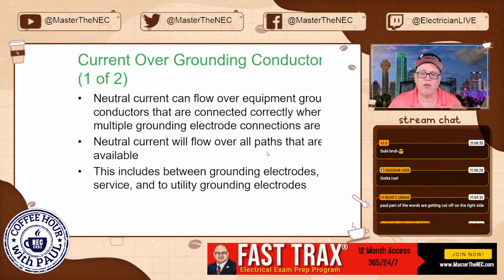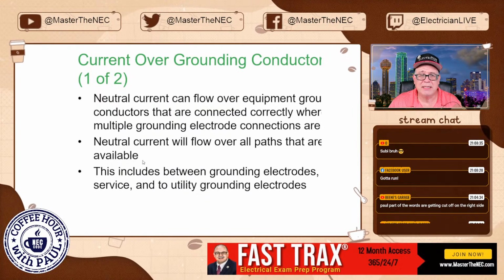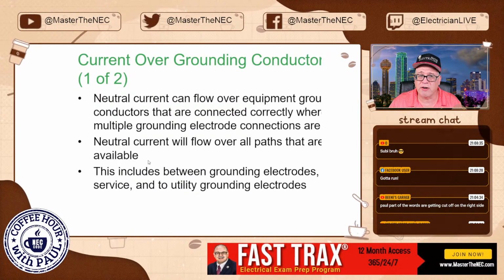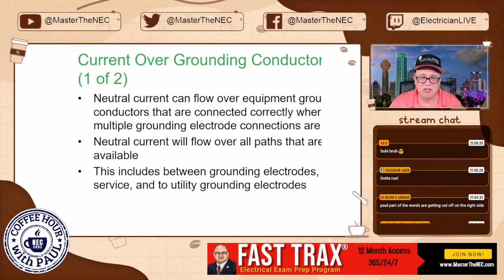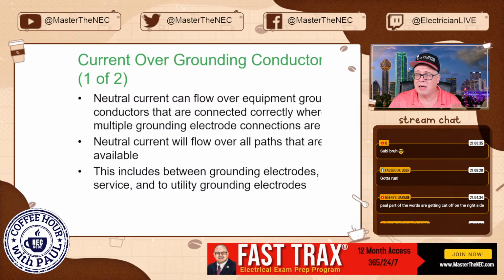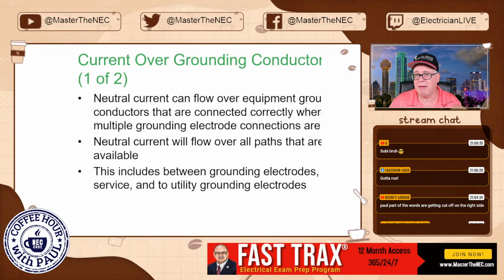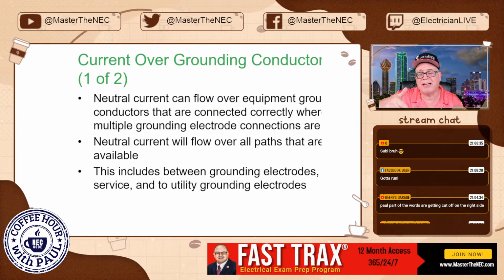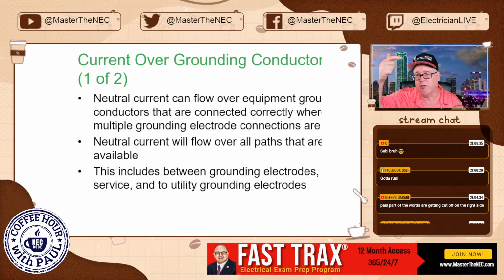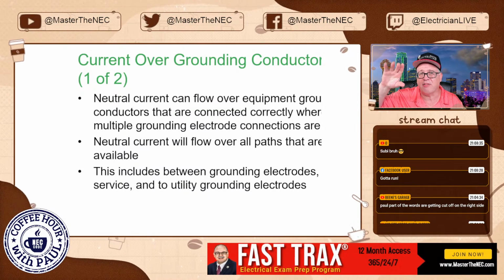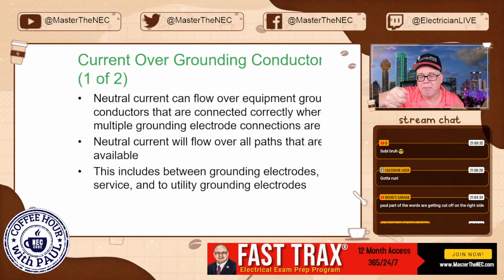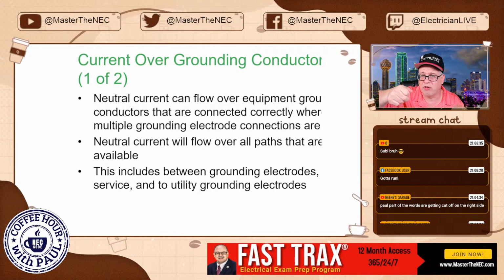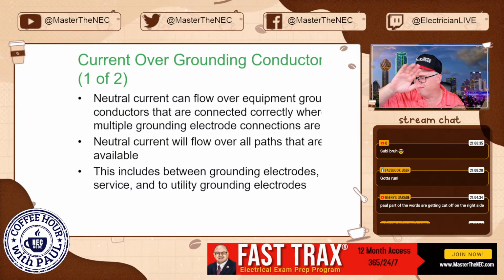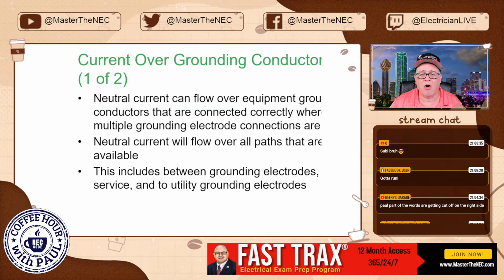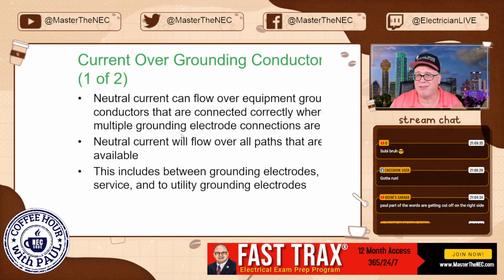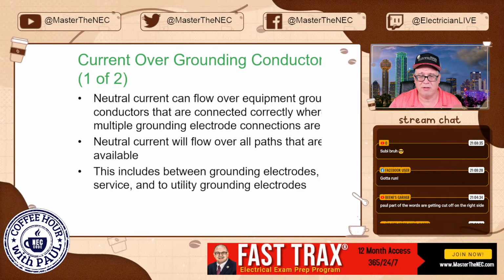Neutral current will flow over all paths that are available. Absolutely. So if you connect that neutral conductor improperly to something downstream, whether it's in a junction box or whatnot, bootleg grounds happen all the time in order to fool those little 3 lights, and they'll make a connection over to the actual receptacle, over to the neutral, and then they put it to a metal box and it fools that little light. But now what you've done is you've energized that metal box. People don't realize the harm that they can do by just trying to get past the home inspection. You create a hazard, okay?